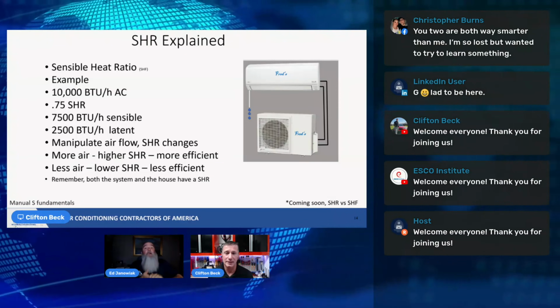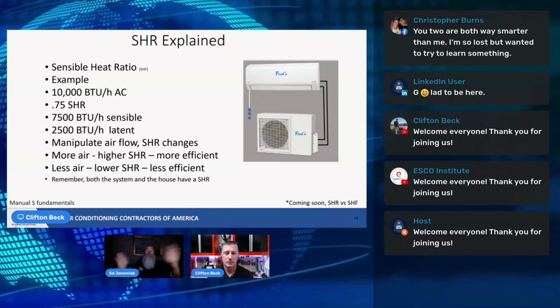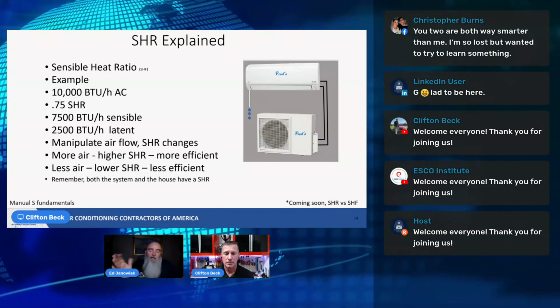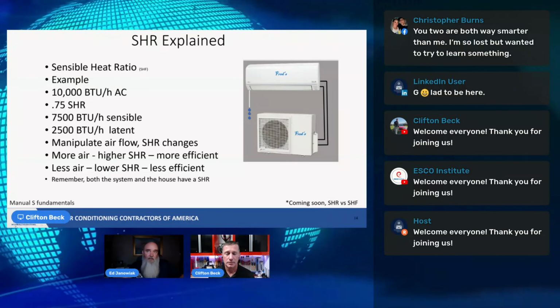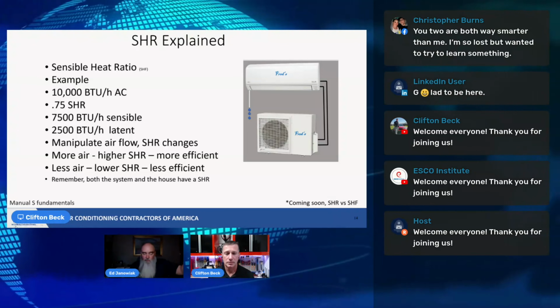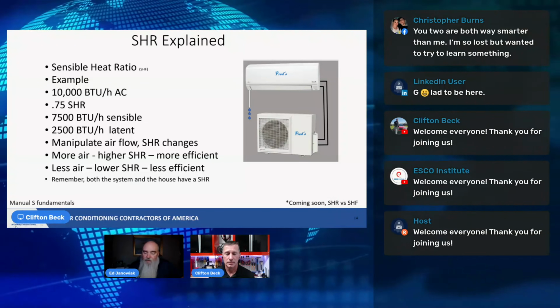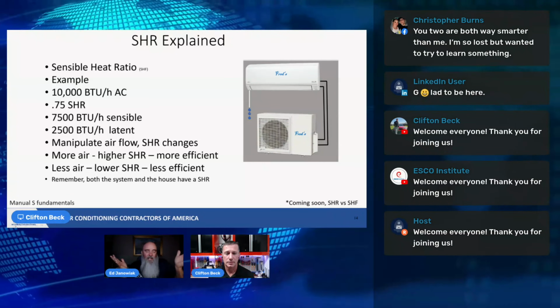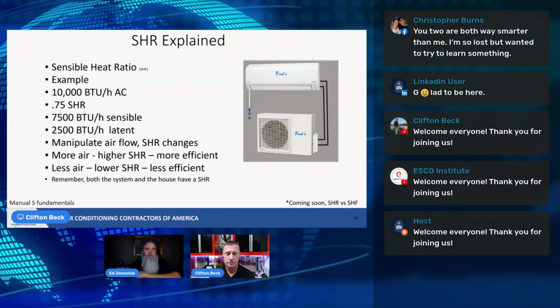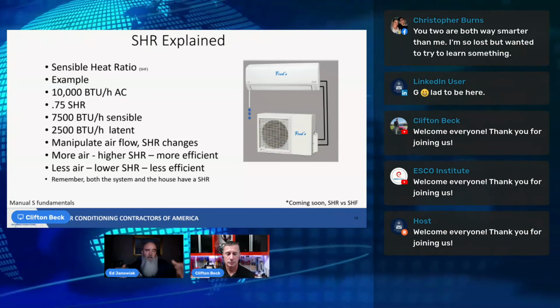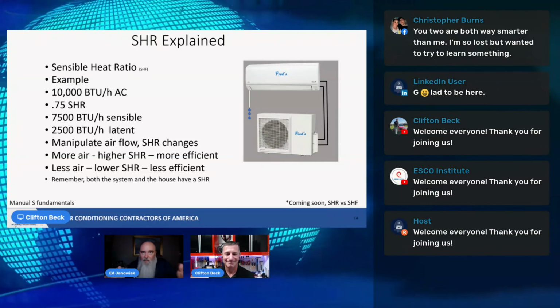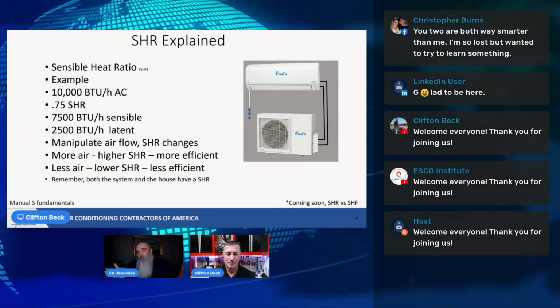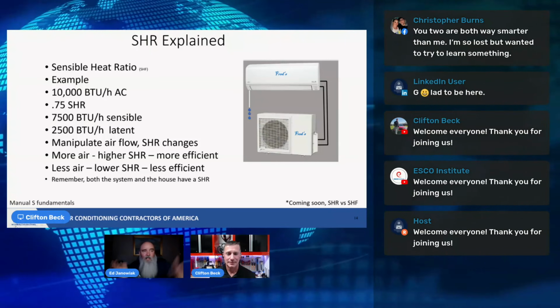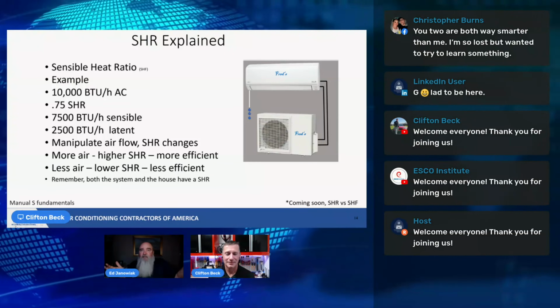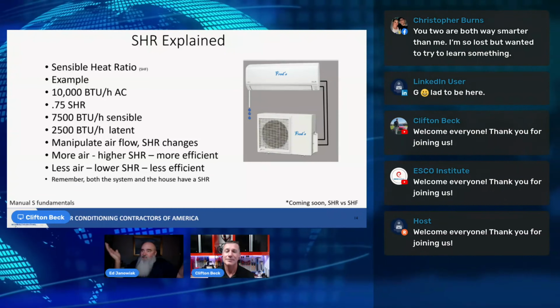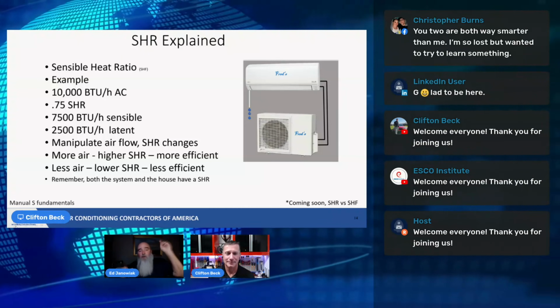Absolutely, because then we're going to be working on sensible heat and changing the calculation. But the whole thing comes back to this: on non-design days, we have to be able to maintain humidity. In fact, when I was talking to this gentleman that's having an issue Tuesday, I was explaining to him, to be very blunt, and I was kind of harsh when I said it, I don't care about the operating characteristics of an air conditioner on a hot design day, because it's running. It's going to dehumidify. The temperature might go up a degree or 3, but you're going to be well under that 50% RH target. So if it's 77, but I'm at 43% RH, I still got a 62-degree wet bulb, and you should be comfortable. Quit staring at the thermostat.